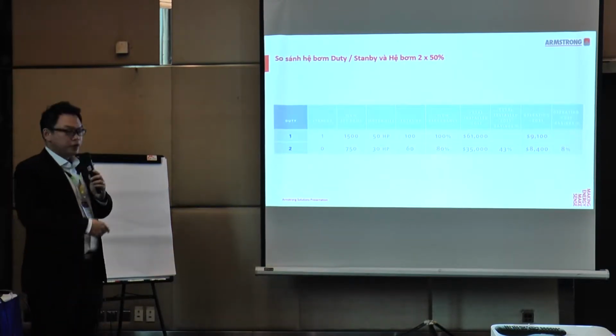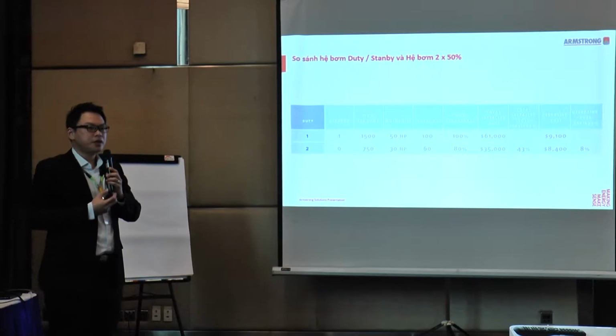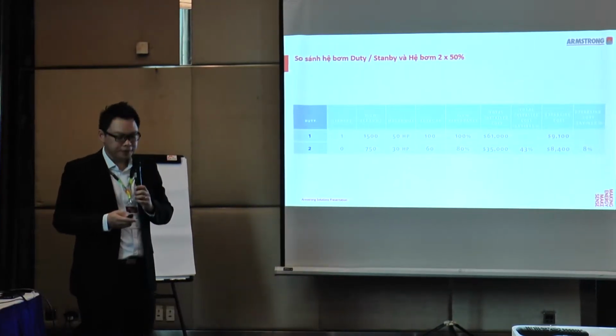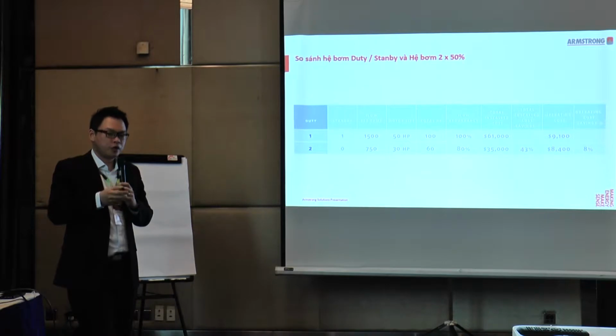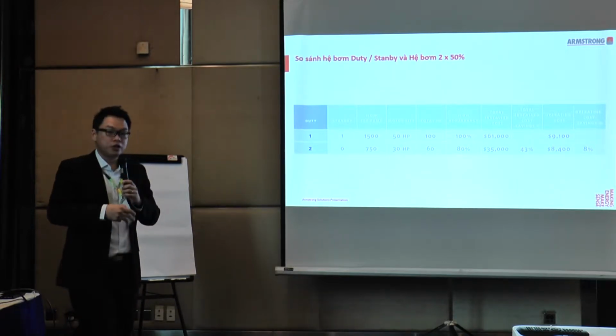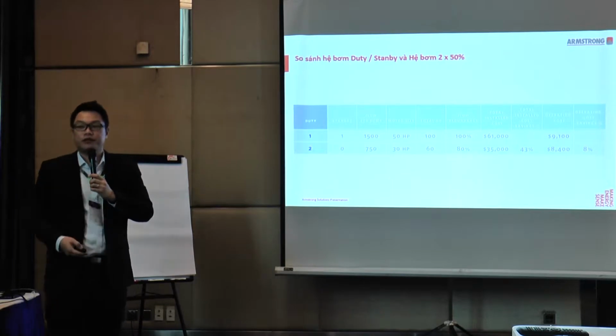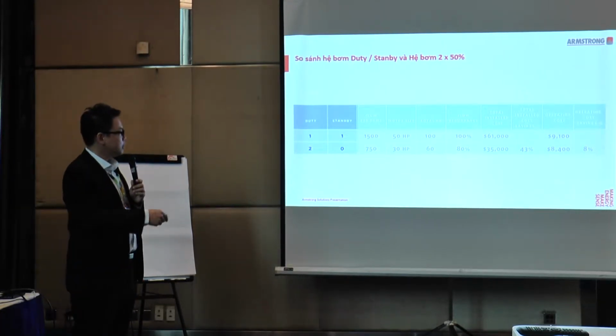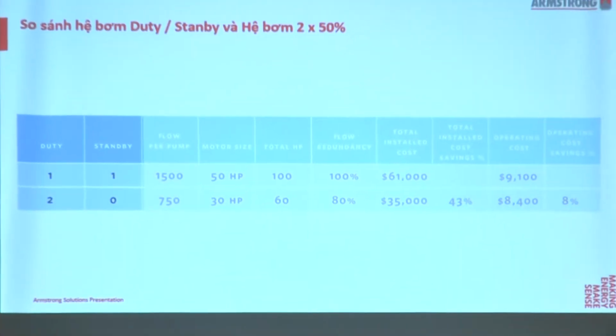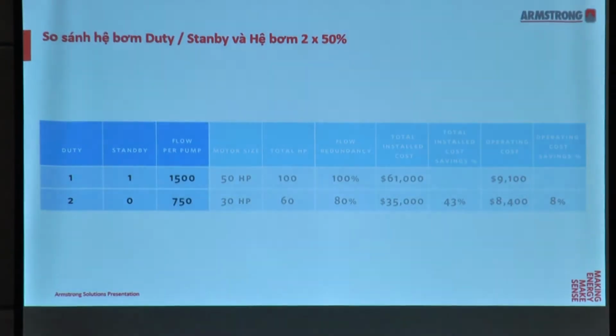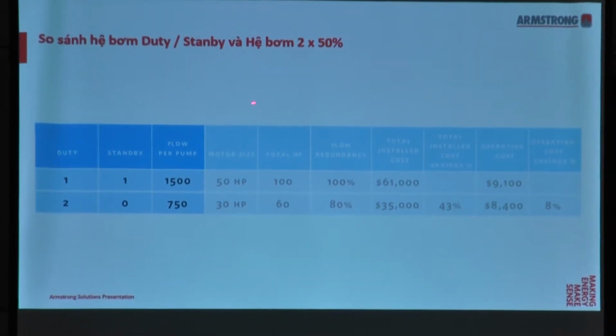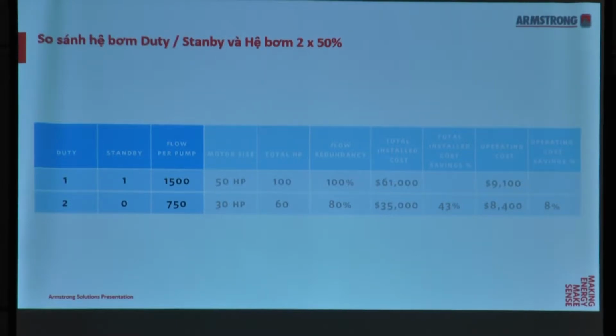So again, I would like to give just some numbers, because numbers don't lie and numbers tell a lot of story. Here I'm comparing 2 scenarios: one is a duty standby against 2 by 50%. The first row here is 1 duty, 1 standby. The second row is 2 by 50%. Okay. So if you were to do the sizing, this is the flow rate per pump. The motor size will reduce for the 2 by 50%. And the redundancy, of course, we have shown earlier on.